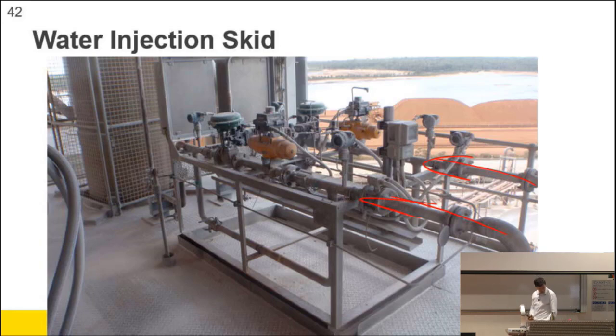So this is coming in, and we've got valves here that open and close, and they open and close varying amounts, because you can't take the gas stream below 130 degrees, otherwise the sulfur that's in it will condense out as sulfuric acid and eat away your steel pipes. So you need to control the temperature fairly carefully. And so you've got variable water injection.